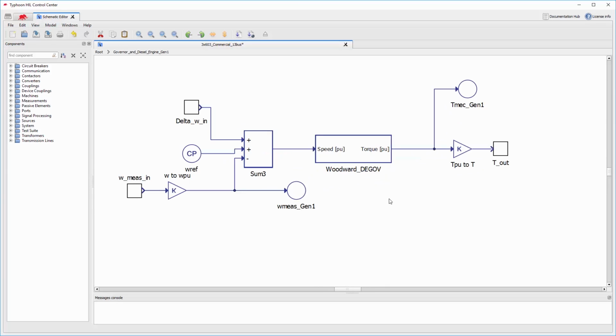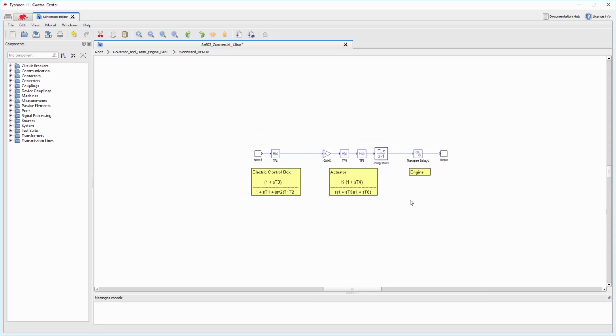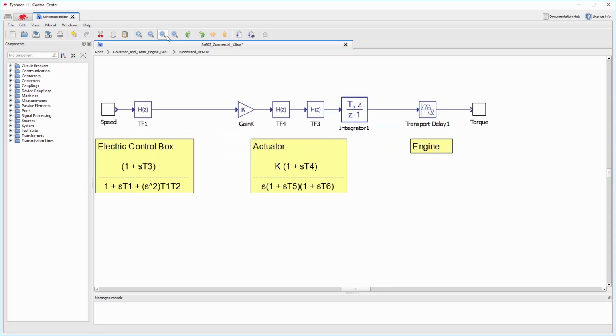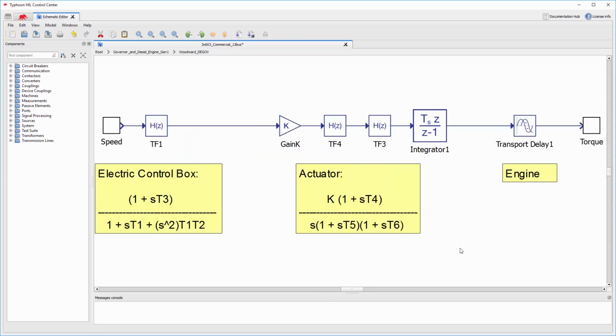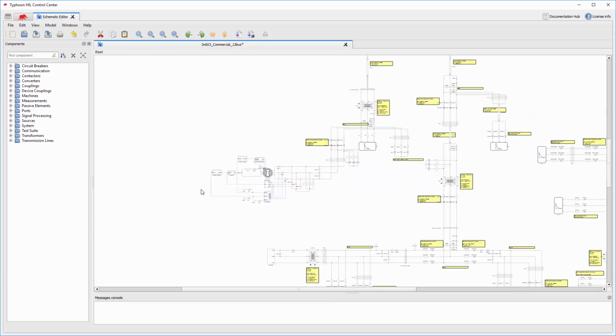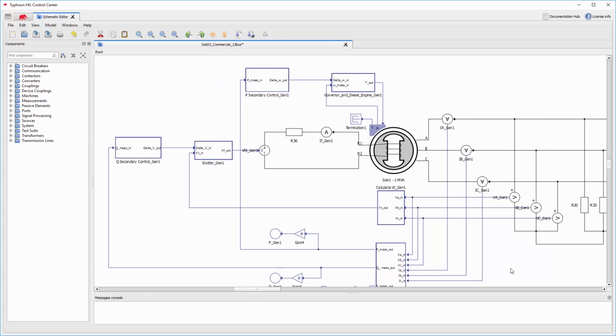In this simulation, we implemented the DE-Gov governor from Woodward. Its dynamic behavior is represented by the electric control box and actuator transfer functions, while the engine dynamic is represented by a simple time delay. As with the exciters, we have IEEE governor and steam turbine elements available in our library. The inner control loops described up to now are the same for both Gen 1 and Gen 2. The difference between them starts with the secondary control loops.